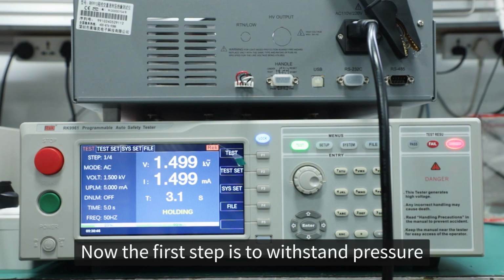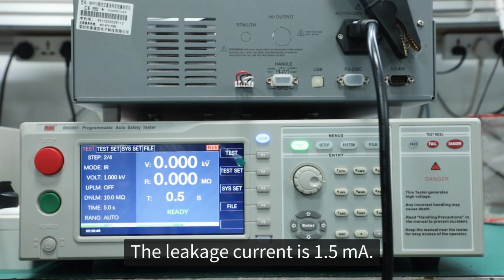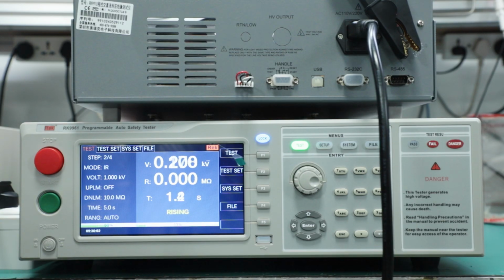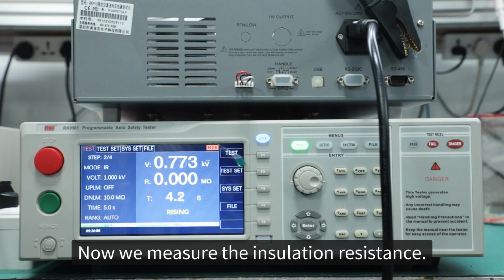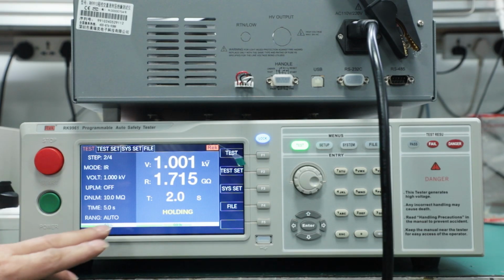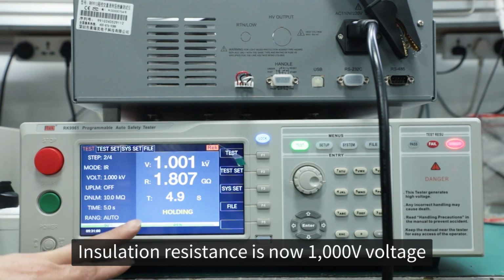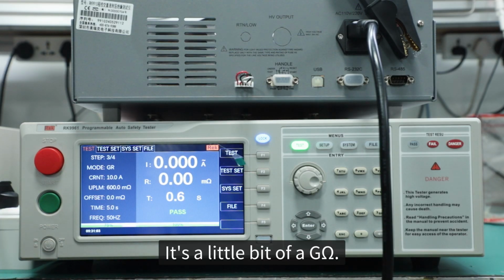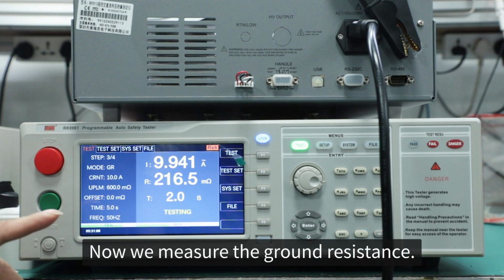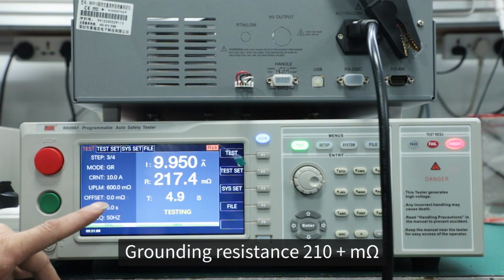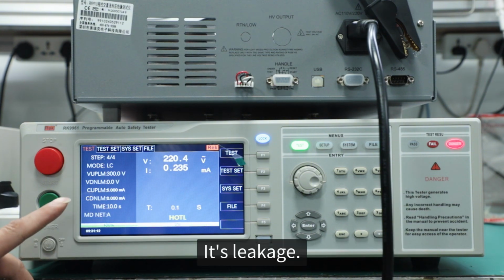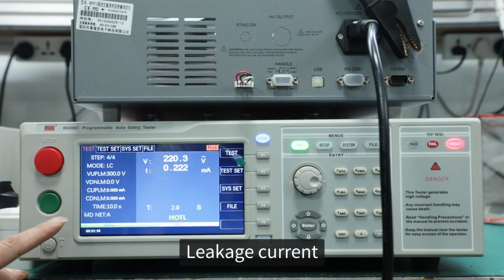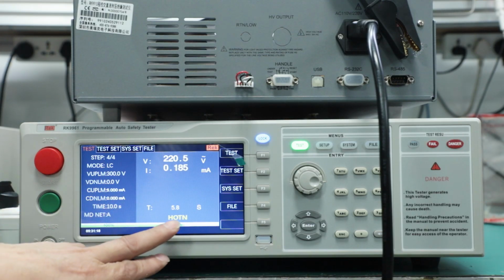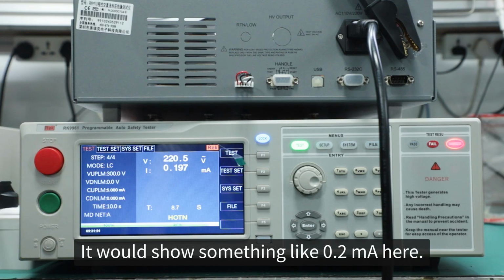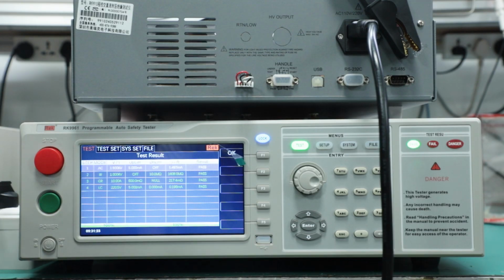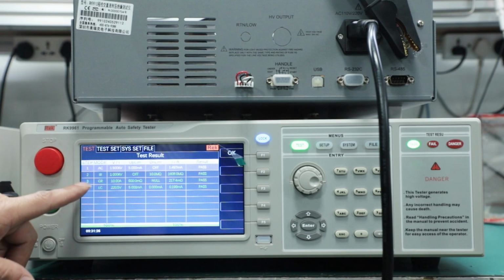Now the first step is the withstand voltage test. The leakage current is 1.5 milliamperes. Now we measure the insulation resistance. Insulation resistance is now at 1000 volts, a little bit of a G, almost 2G. Now we measure the ground resistance. Grounding resistance 210 plus milliohm. Then leakage current, with live wire and neutral wire, would show something like 0.2 milliamperes here. These items are all tested.